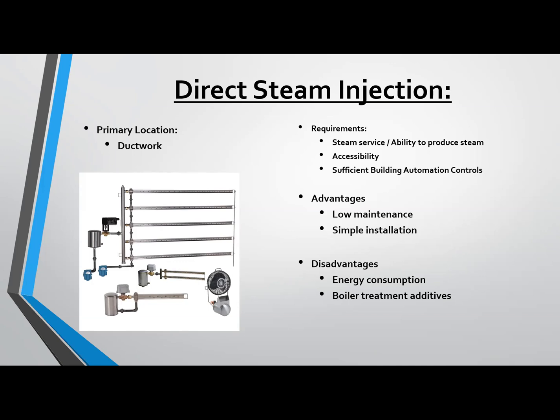The first most common way of putting humidification into facilities is a method called direct steam injection. This particular piece of equipment here is made by DriSteem. It's essentially called a direct steam injection humidifier. It's a series of tubes and nozzles that are cut into the duct, not far from the fan, and sprays the humidity into the duct, which is then carried throughout the facility. DriSteem is just one of the many vendors out there that does this. This was the one I had the most product information currently available on.